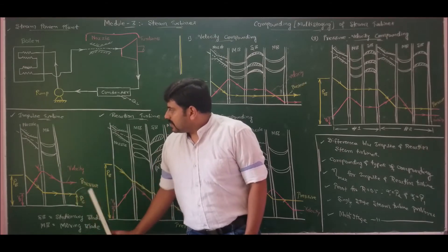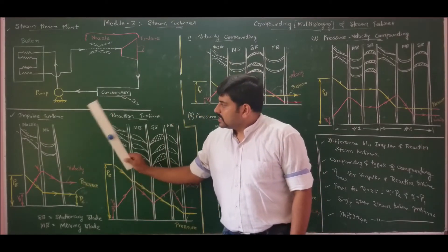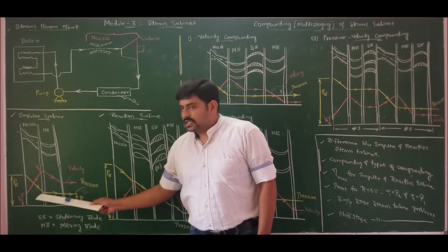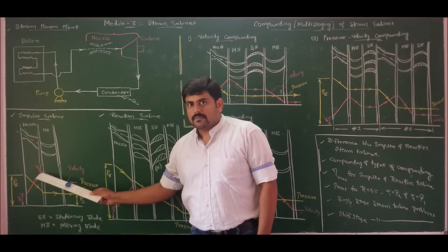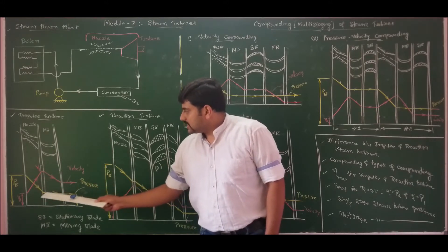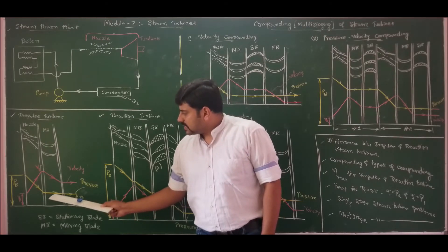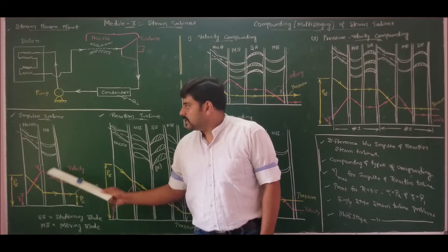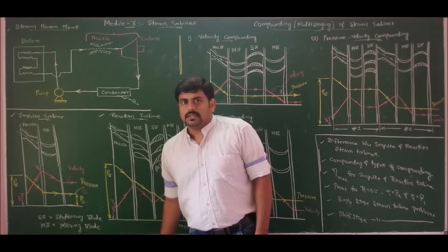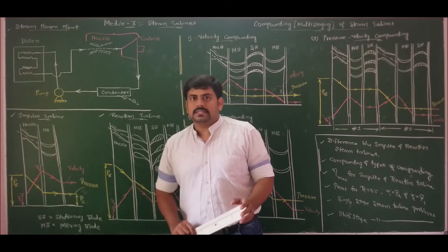For an impulse turbine, observing the variation of pressure and velocity over the steam passage length: in the nozzle, pressure drop is observed and velocity increases. In the moving blades, velocity decreases whereas pressure remains constant. Since pressure is constant, there is no change in enthalpy in the moving blade — the change in enthalpy occurs only in the nozzle. That is, steam expands completely in the nozzle for the impulse turbine.